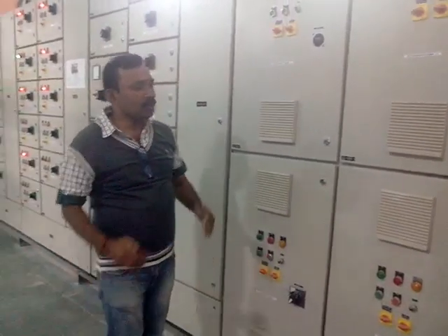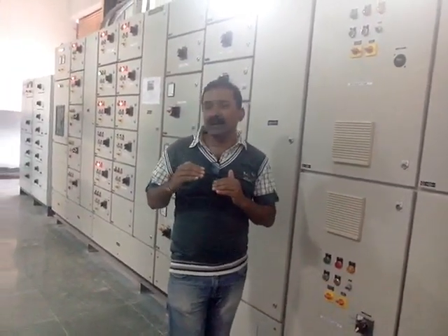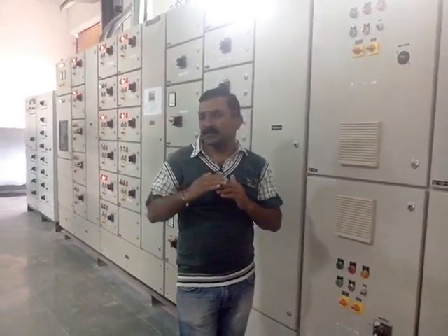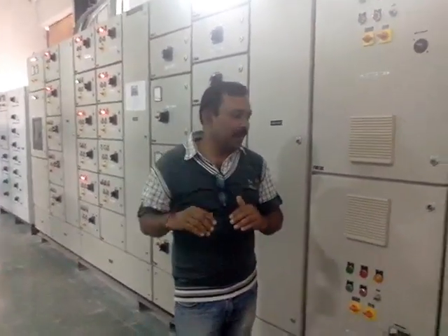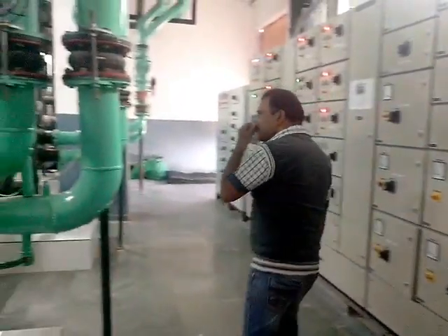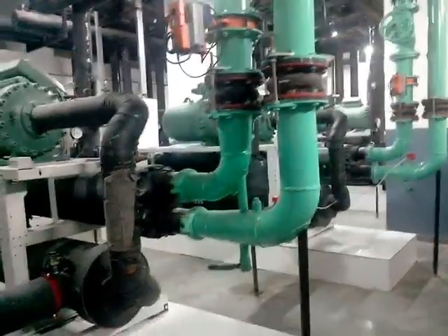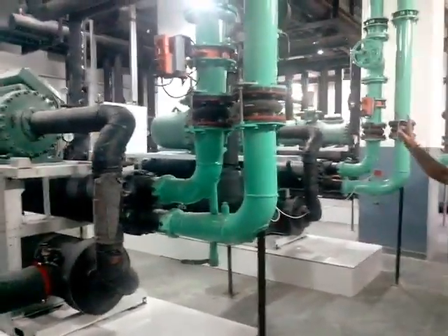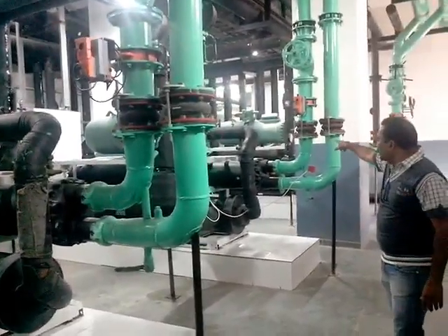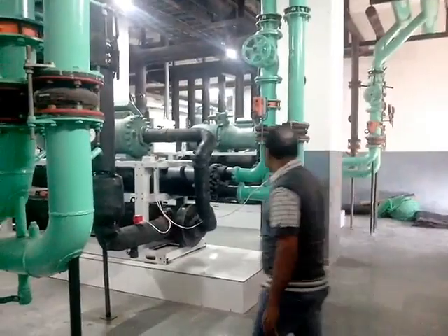When the air condition load is less, the back pressure sensor gives command to secondary pump starter and lowers the speed of pump. Thus we save a huge energy. We have 3 chillers of 150 TR each. Chiller 1, 2, 3. Third chiller plant is with desuperheater. We get a hot water from waste energy.